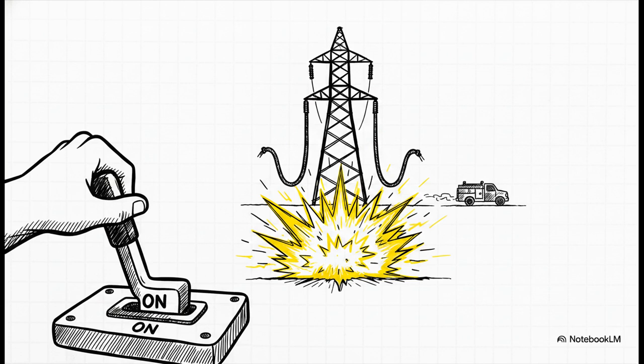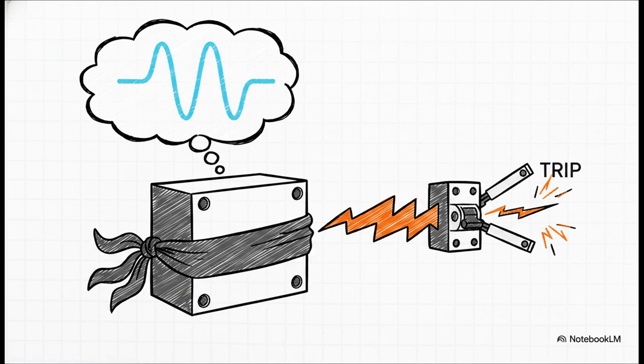That brings us to switch on to fault. Closing into a grounded line creates a uniquely dangerous zero-voltage nightmare. Because the fault is perfectly solid right at the very start, there is virtually zero voltage present the exact instant the breaker closes. Remember our math from earlier? The relay strictly needs voltage to calculate impedance. Without a voltage reference, the normal distance zones go completely blind. They might not trip at all.